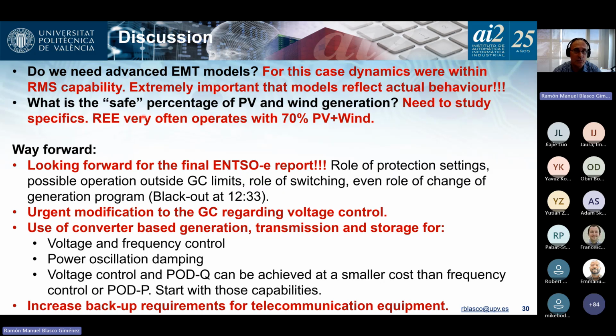What's the safe percentage of PV and wind generation? That needs to be studied specifically, but in Spain and Portugal, today they are operating at 70% PV plus wind. This is almost the same every day. So in a system that is almost isolated, 70% would be reasonably safe. Pushing that higher, which would be required if we want to reach the decarbonization targets, gets technically more challenging.